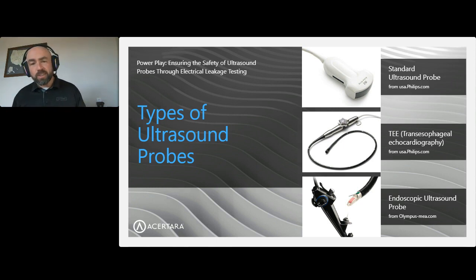And then finally, I would say the one that is most likely to be seen besides TEE probes in sterile processing would be endocavity probes. So that would be endovaginal and endorectal probes. And those each are characterized by kind of a long shaft with the ultrasound array at the end. They typically have what we call a very tightly curved array, and that gives the sonographer or physician a very wide field of view when they actually go to do their procedures. So those are the standard ultrasound probes, in large categories and in broad swaths.